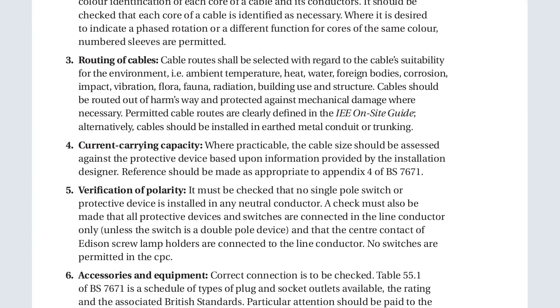Another one is the current-carrying capacity. We have to make sure that the capacity is also catered for, that is, where practicable, the cable size should be assessed against the protective device, based upon the information provided by the installation designer. A reference should be made as appropriate in the index.